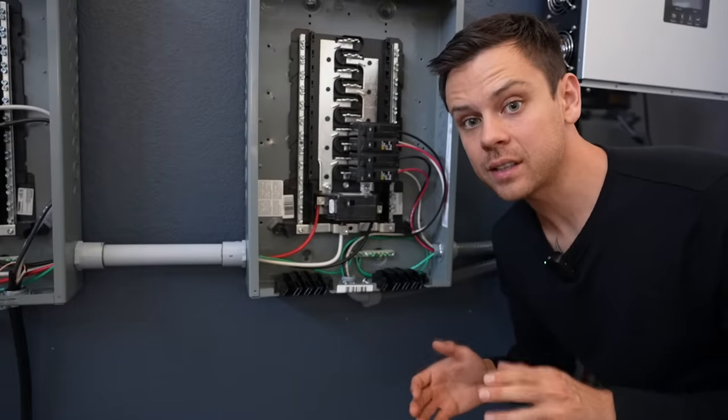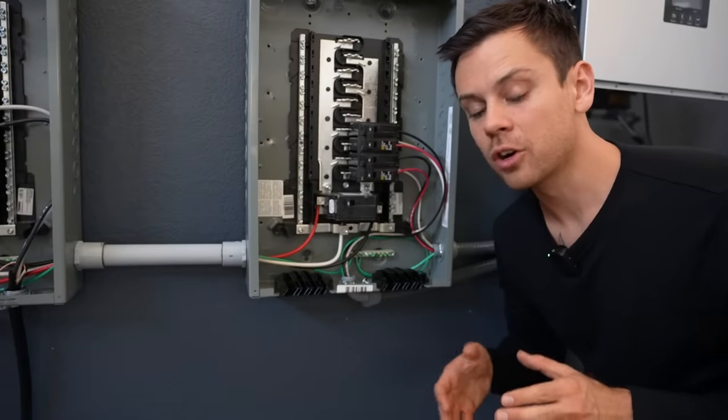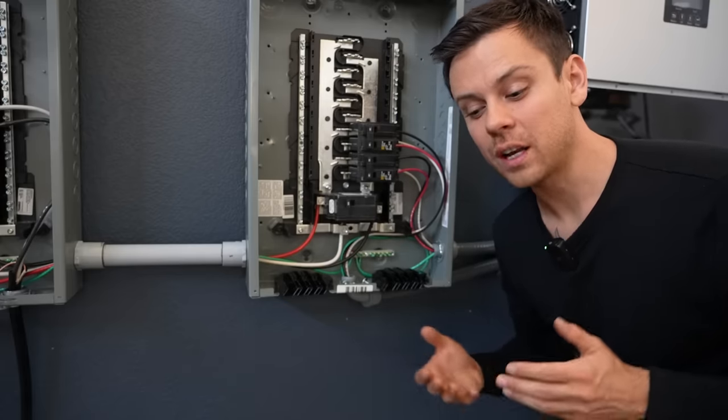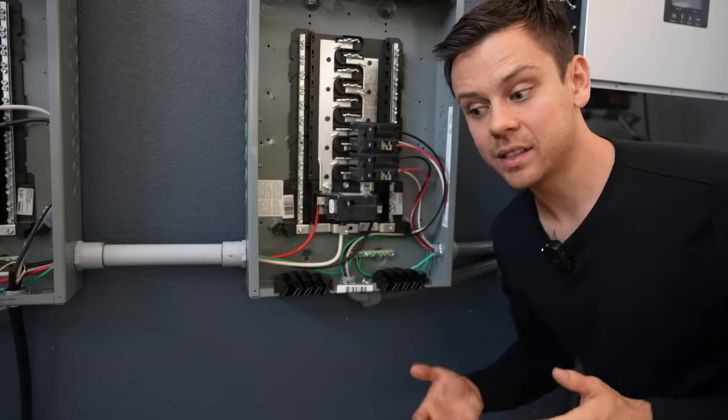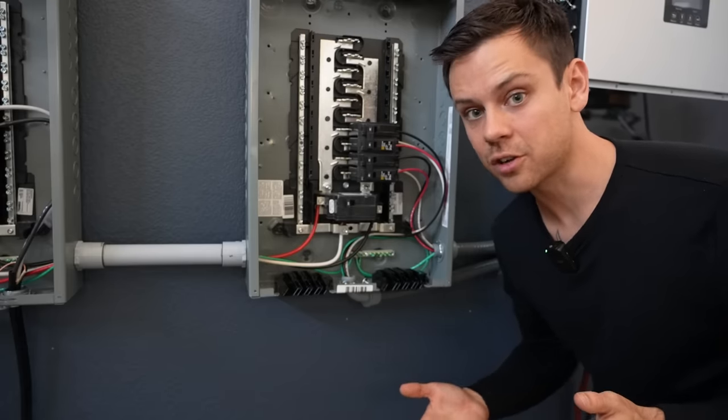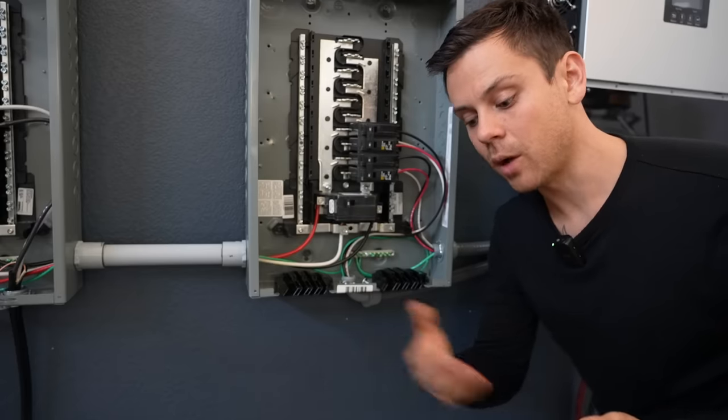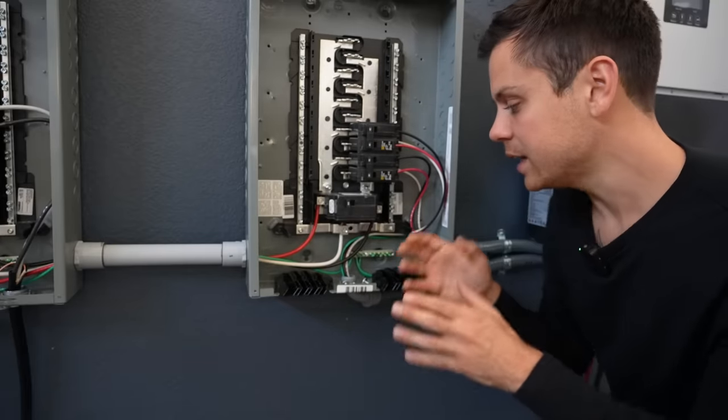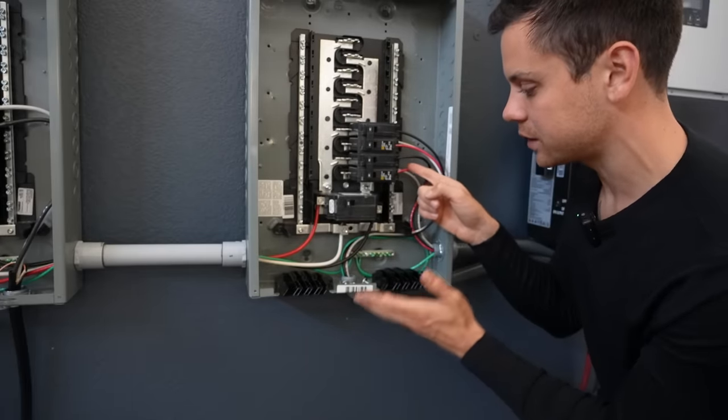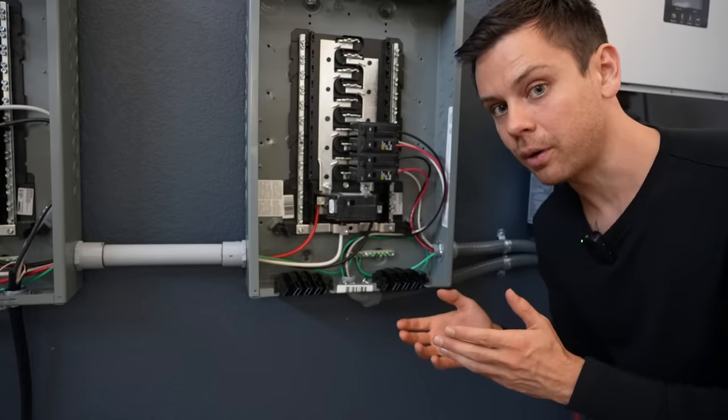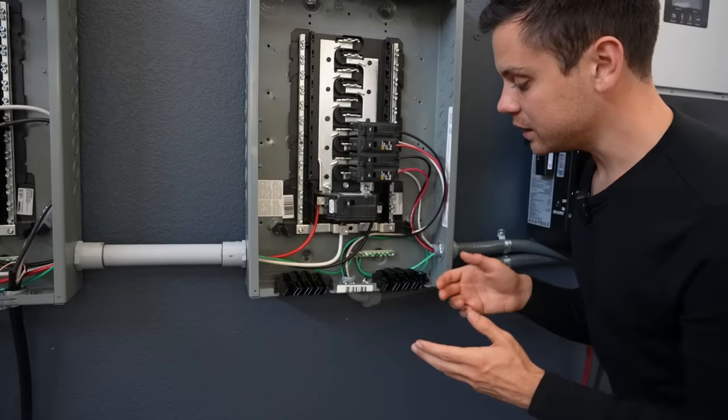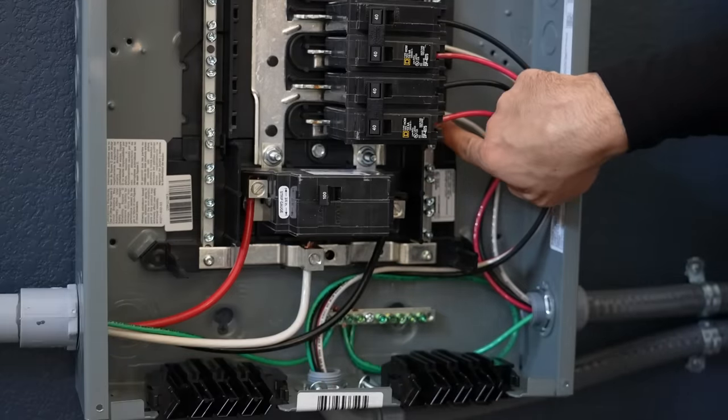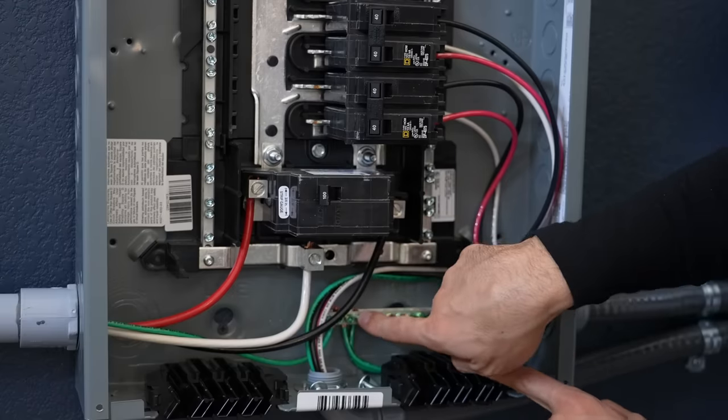Now the neutrals and the grounds need to be separated with this system. These inverters have their own ground neutral bond relay. And what that means is that depending on the situation it will create a bond where it's necessary. But if it doesn't need it, in the case of a pass-through, that's a feature that these have. If you're connected to the grid and it wants to power the loads and there's no more battery power or solar power, it will pass through the power from the grid. In that situation you want to keep the neutrals and the ground separate. So you have to install your own ground bus bar for the ground conductors.